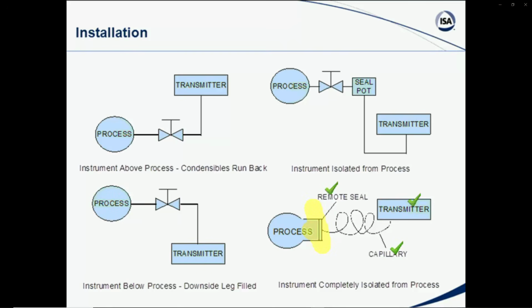So the process is on one side. The other side then is a filled, sealed system, the capillary tubing running back to the transmitter, and therefore the transmitter will not be exposed to any of the process. And again, you have to take care of the capillary tubing. It's a filled, sealed system, and as I've seen in the field in past times, you don't cut and splice that if you have too much capillary there.